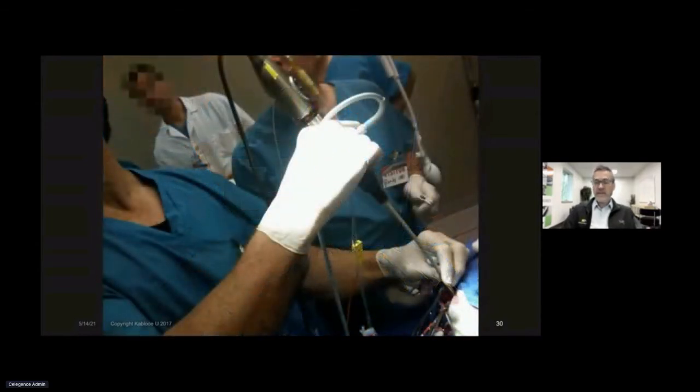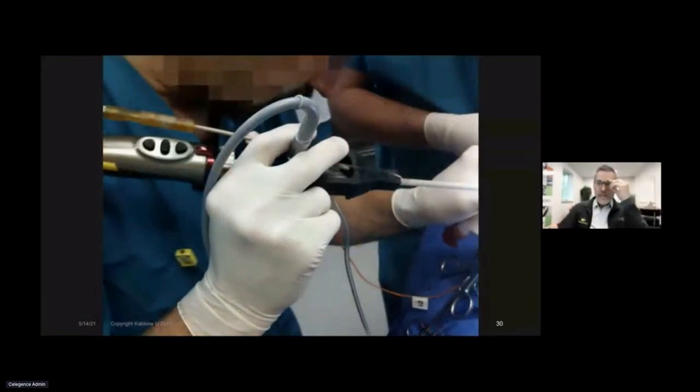So the user interface on this device was very much a hand-controlled, manipulated user interface. And we're concerned about what his hand is doing, especially when his attention is elsewhere. You can see the user is obviously looking somewhere else for information, but yet their hand has to be interacting with the device. That's important human factors engineering data. During different phases of the device, the hand switches to different controls. It's controlling different things. That's important data.